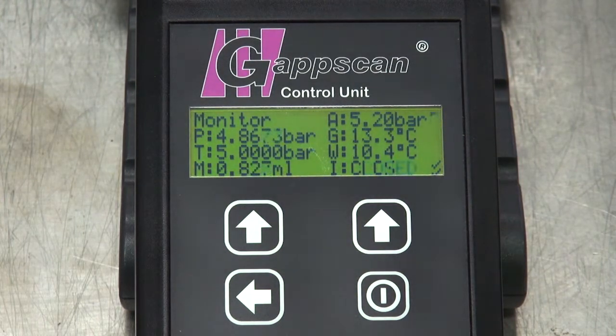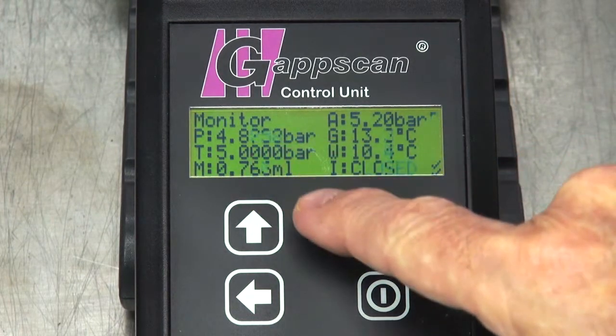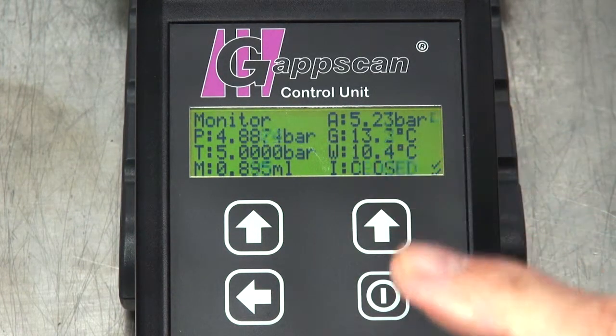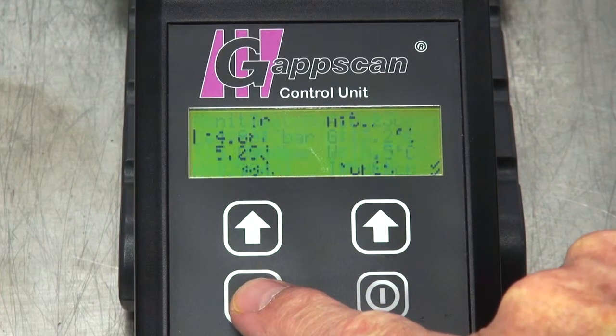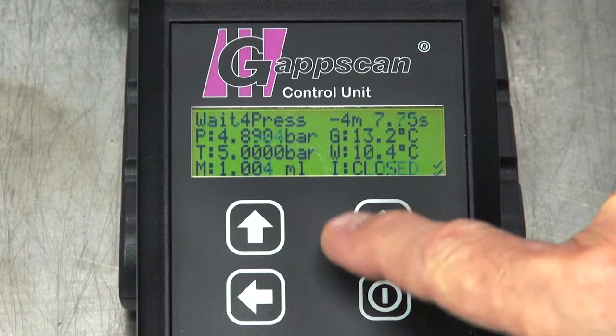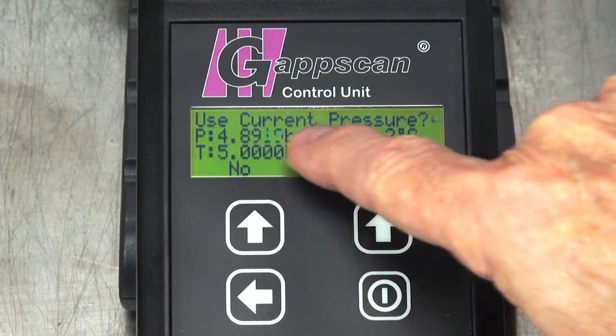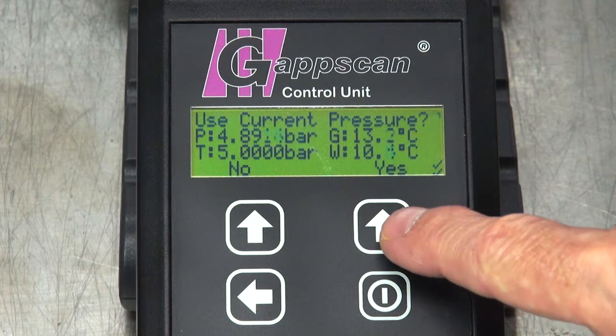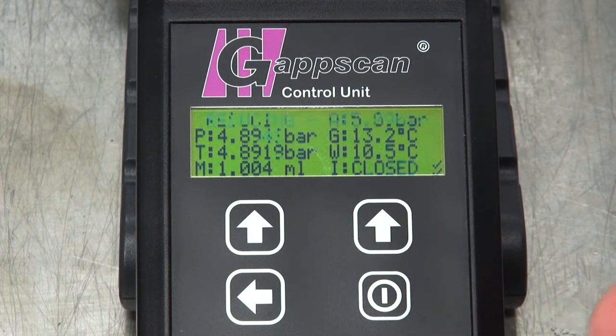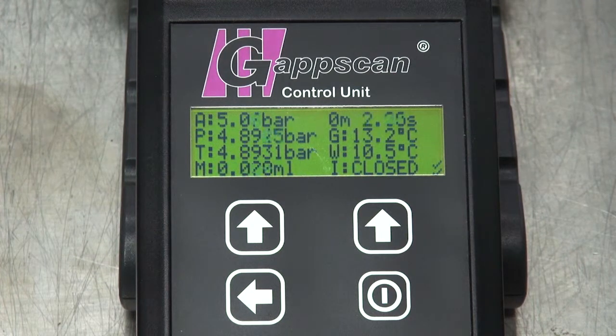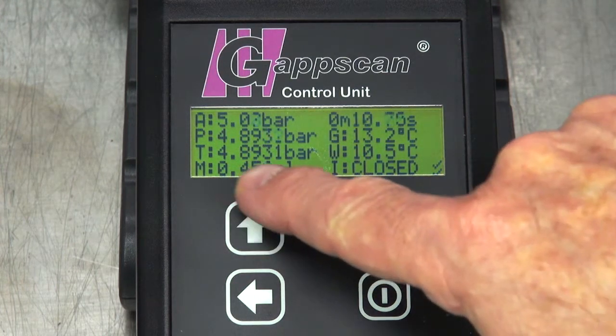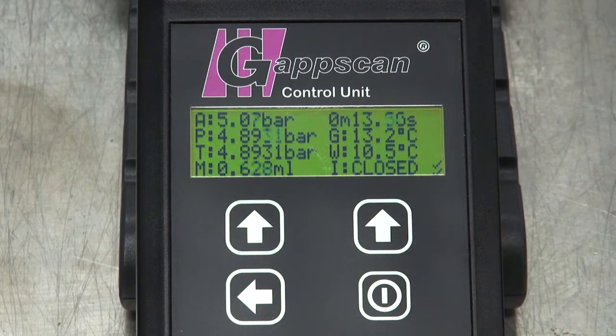In this case, it does not quite reach 5 bar as the maximum mains water pressure is nearer to 4.9 bar. Press the return key. Select Test. Press the I/O key. You will be asked if you want to use the current pressure. Select Yes. Once stabilised, the test will run automatically. You can see it is failing more quickly at the higher pressure.